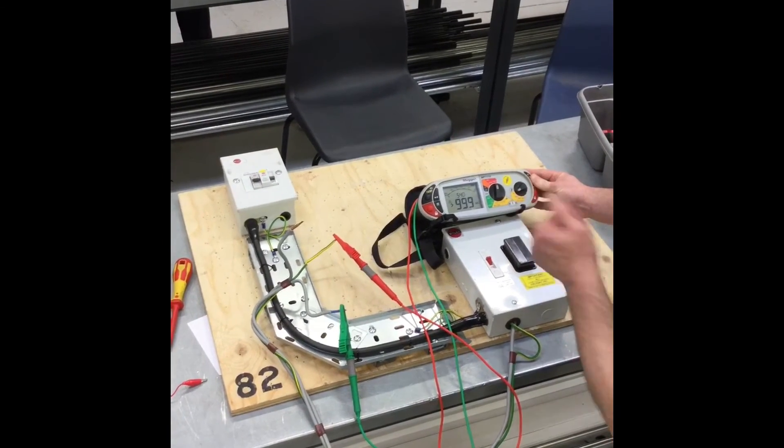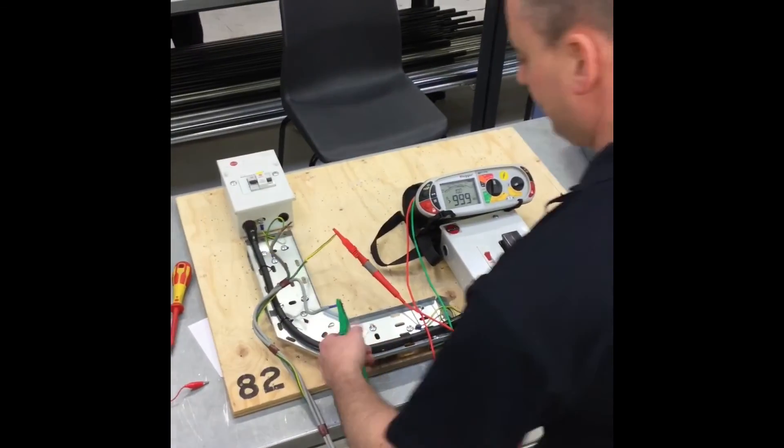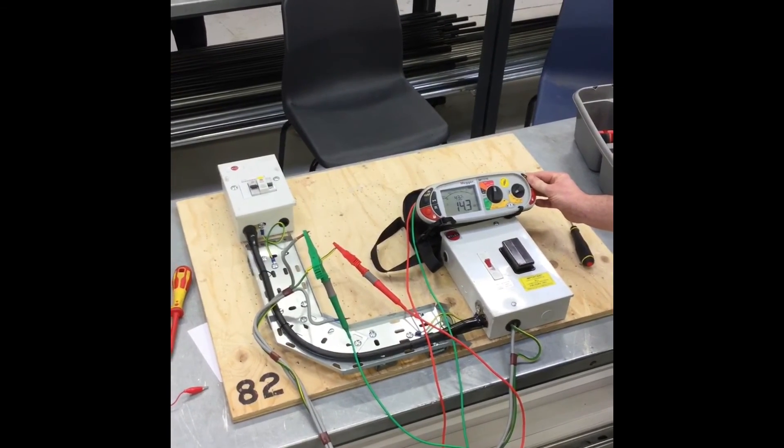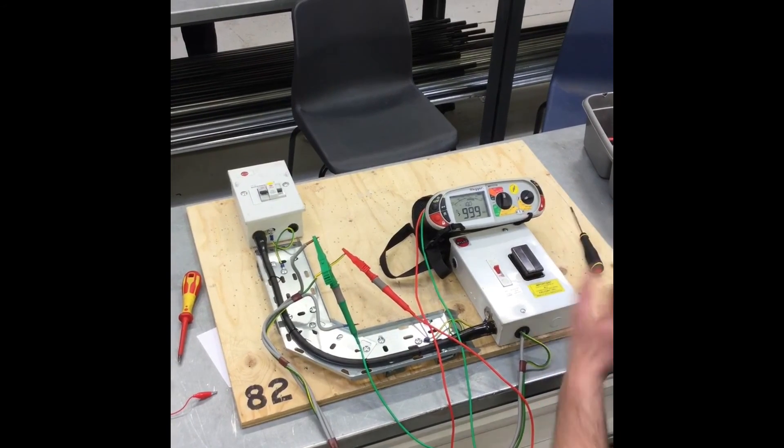Repress. Insulation resistance greater than 999. And then the final one, and again. Check paperwork, record all three readings.